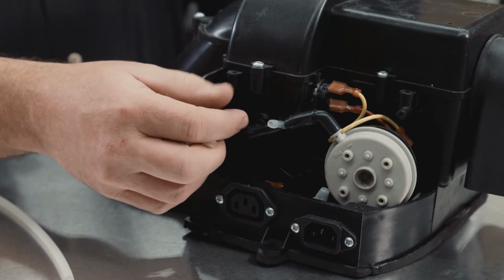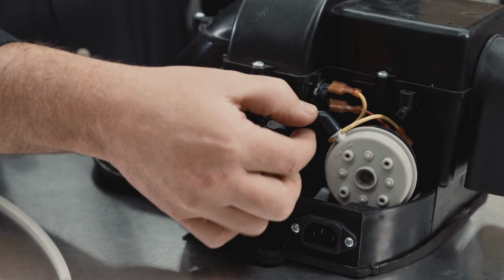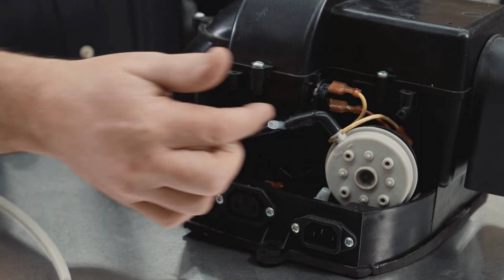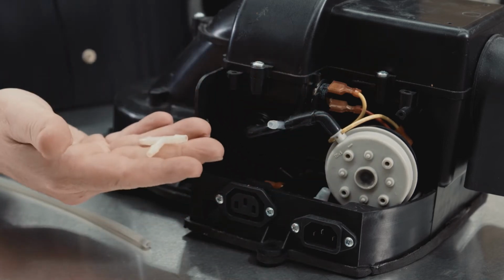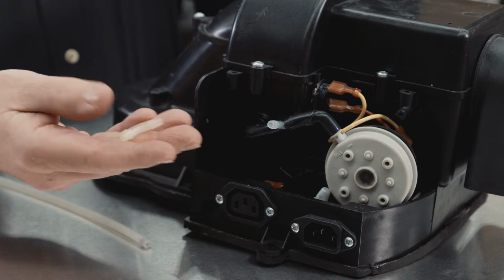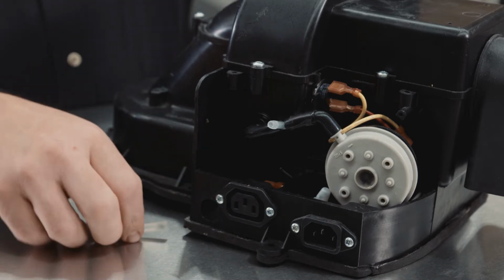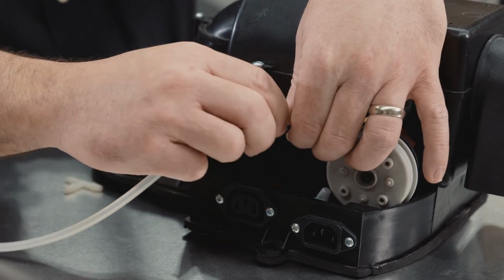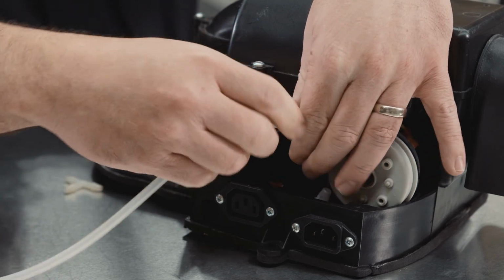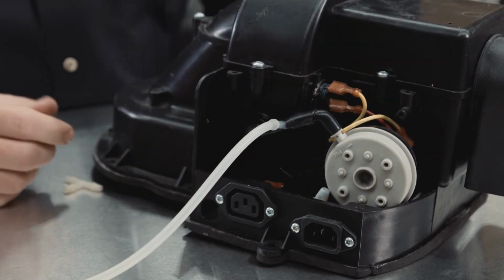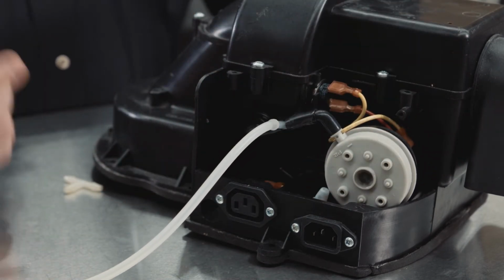For testing our pressure switch, I've cut the tubing that goes from the switch to the fan assembly and put in place an inline T connector that the manometer connects to. The manometer tubing goes directly to that T. When the fan assembly is on, we'll record the vacuum.